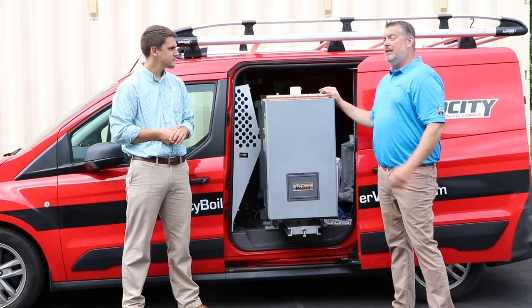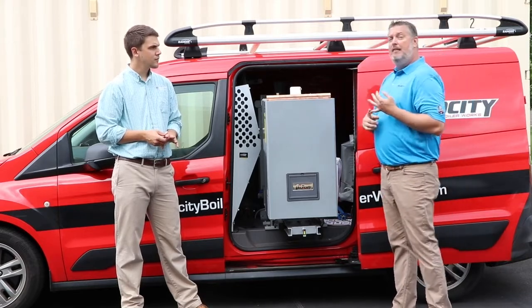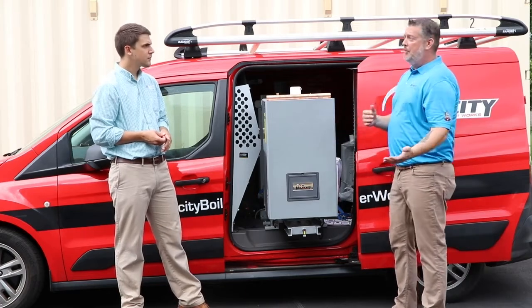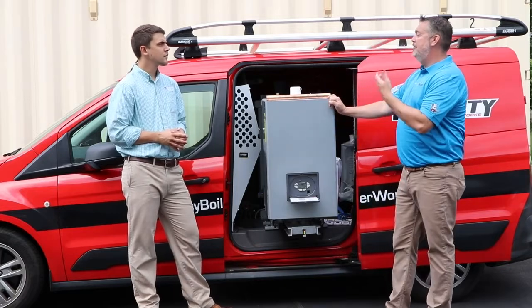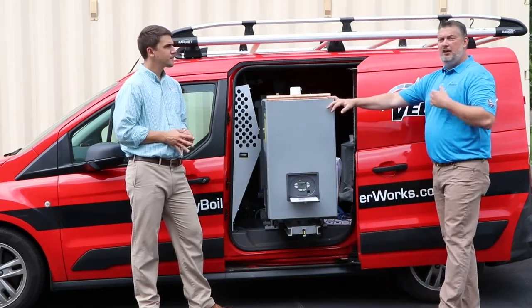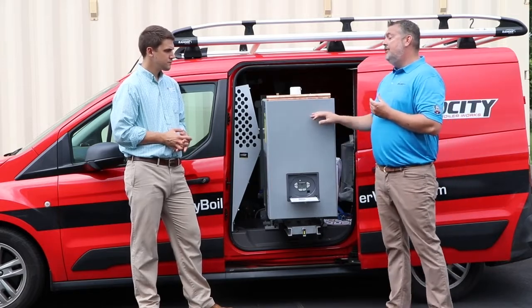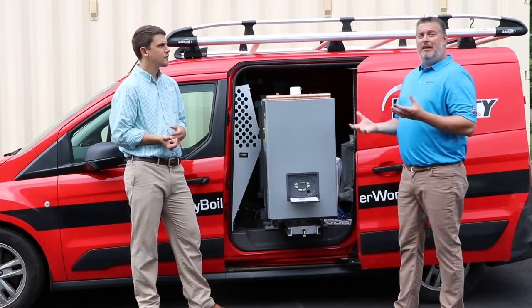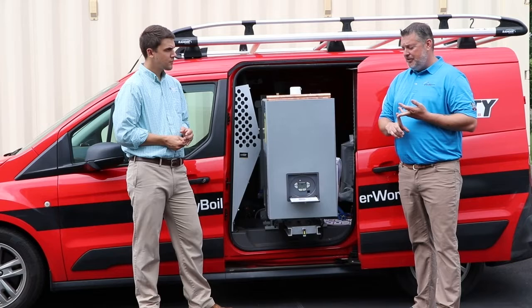Pat stands for Phantom Adaptive Technology. It sounds like a big term, but it's actually really simple — it's going to help you with your installations. One of the things Pat will do is find the home's heating curve. How many contractors before would have to set up the outdoor reset and go with a generic one doing 0-180, 70-130? Pat will find the optimal heating temperature for each home. There's a boost feature built in, so if it's under temperature and it's really cold outside, it'll start raising the boiler temperature and readjust that curve. The other portion of it is it will adjust its own combustion. Normally, when installing a high-efficiency or condensing boiler, you'd have to use a combustion analyzer to dial the combustion in. Pat's technology does all that for you. The adaptive technology works on the gas and on the temperature control system, basically giving you a hands-off installation. Once it's piped in and you put water, gas, and electric to it, the unit's off to the races — it does all of it by itself.